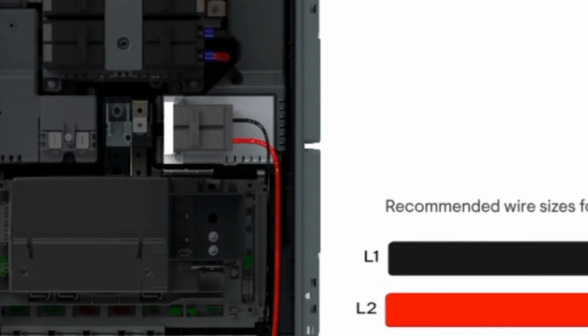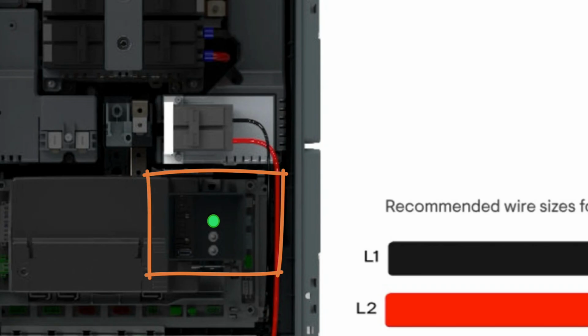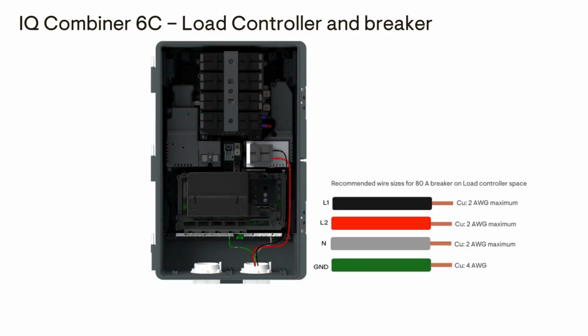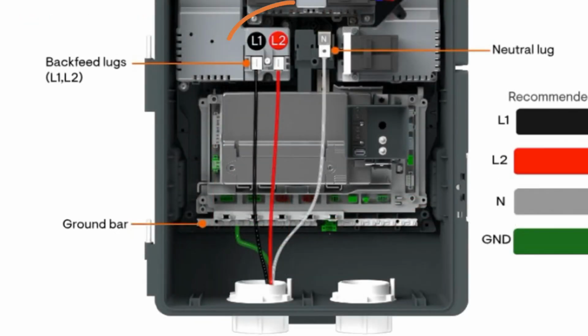Below the load control breaker are combiner status LEDs and a reset button for the integrated IQ gateway. And finally, the Combiner 6C has a pre-installed Cat4 cellular modem, which is intended to provide a backup internet connection. On the center-left functional area of the Combiner 6C are the main backfeed lugs. These are used for connecting the system backfeed conductors to the main electrical panel or backup subpanel.